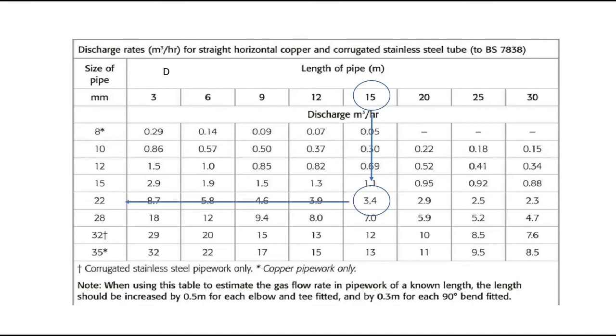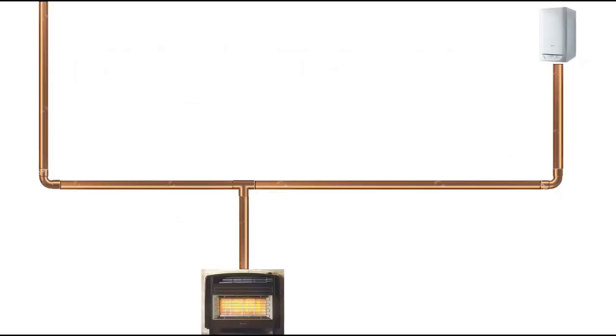We bring that back across the chart, and in this case that needs to be a 22 millimeter diameter pipe. So now we've got all the pipe sizing for our entire installation — the first run is a 22mm pipe, the pipe from B to C needs to be 12 millimeters, and the pipe from B to D needs to be 22 millimeters.